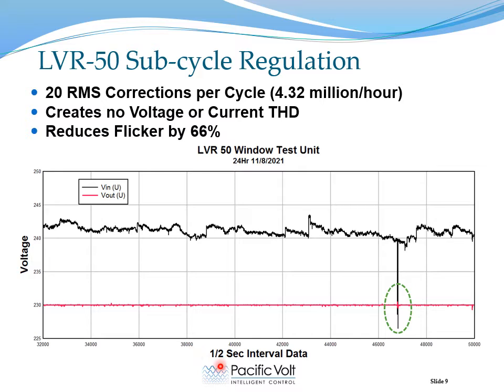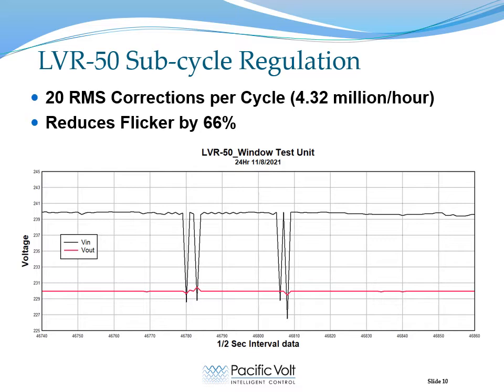In this strip chart, which is half-second interval data, the red line is the output of the regulator and the black line is the input from the grid. You can see a couple places here where the line regulator changed its taps, and here there was an event that caused the regulator to transition from bucking to boosting. We can zoom into that and look at it in more detail because of the high resolution data that is recorded in the regulator. Zooming into the data, we can see that these are actually 4 separate events, and these are the type of events that would cause flicker had we not corrected the output with the regulator.